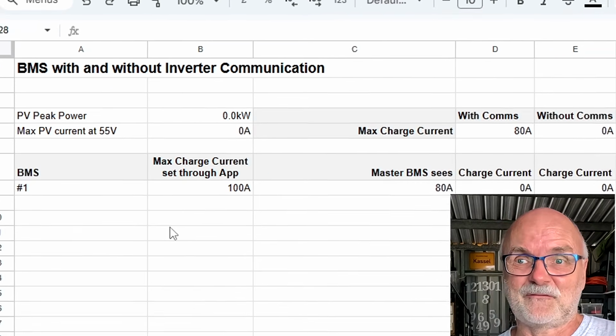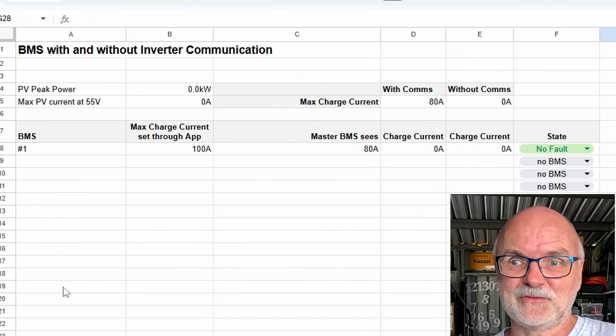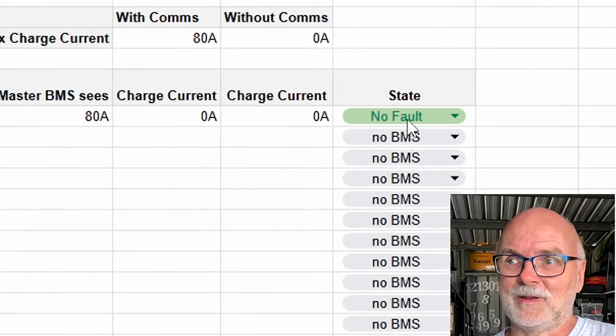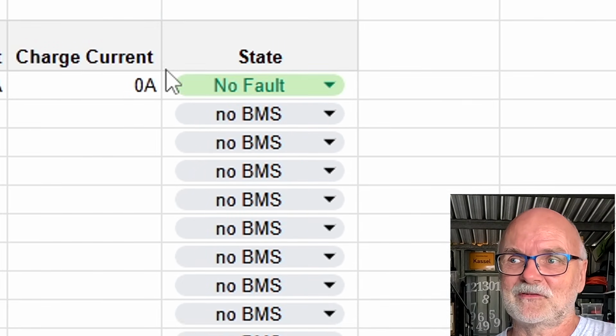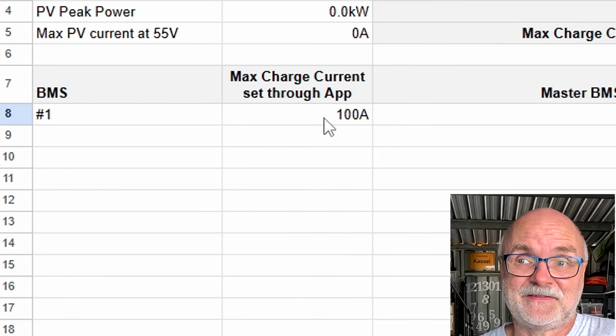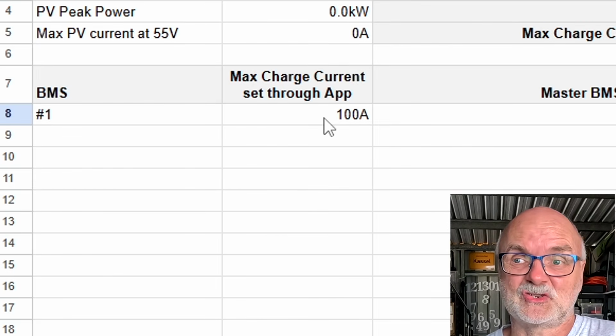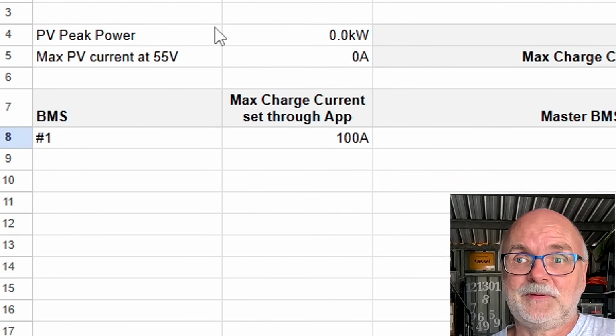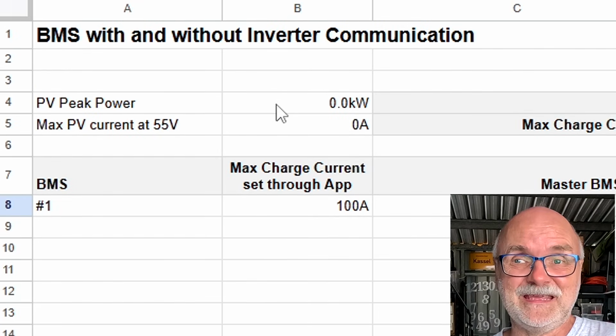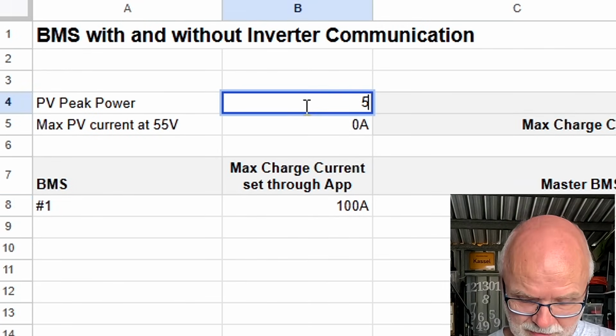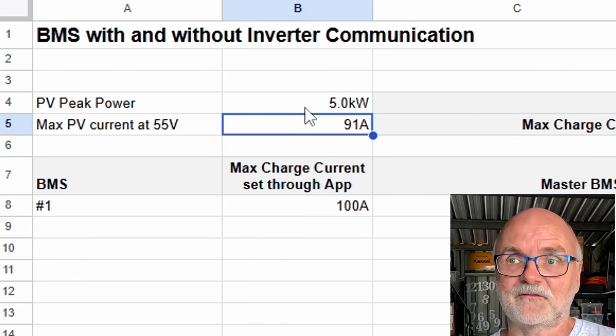So what it consists of, BMS 1 to 16. You can see I've got only one BMS activated at the moment here with this drop-down menu. And this BMS has a charge current of 100 amps. You can change this as well if you want to. And up here I can put in my PV peak power. So let's put in a small solar system of 5 kilowatt.